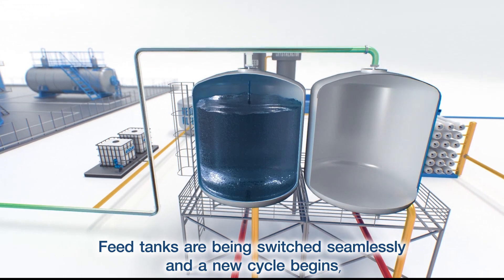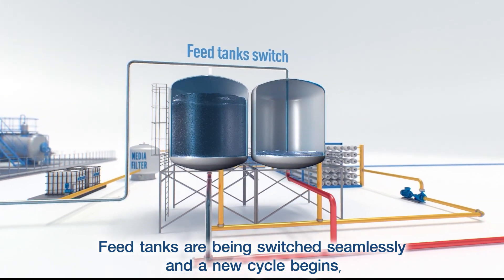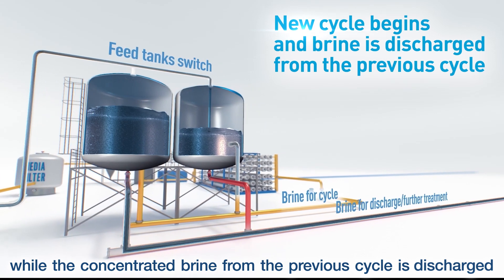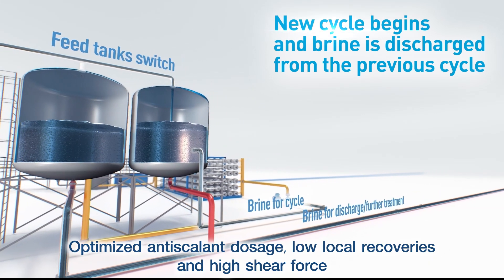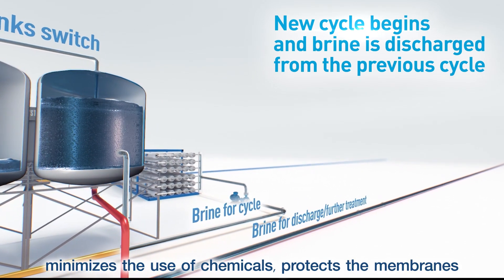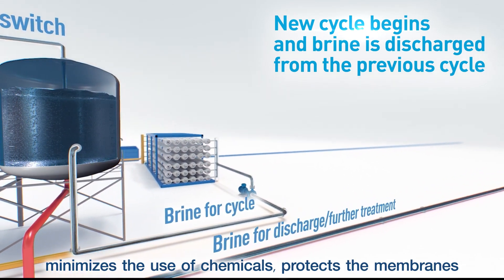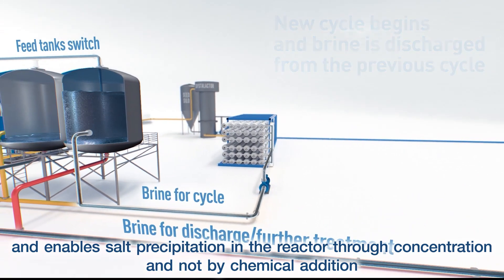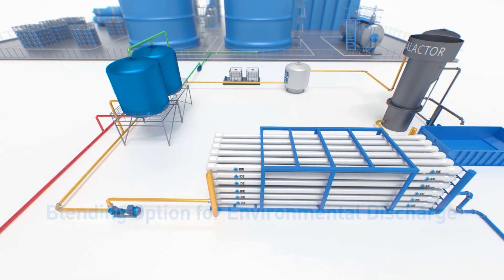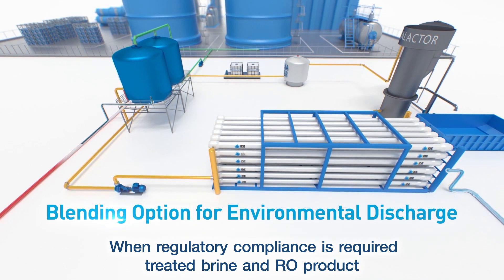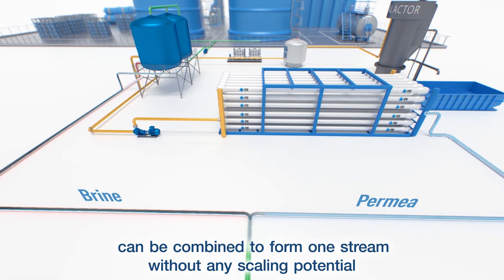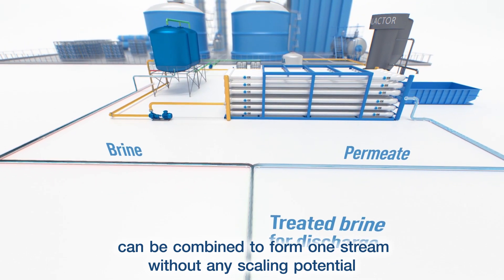Feed tanks are switched seamlessly and a new cycle begins while the concentrated brine from the previous cycle is discharged. Optimized anti-scalant dosage, low local recoveries, and high shear force minimize the use of chemicals, protect the membranes, and enable salt precipitation in the reactor through concentration and not by chemical addition. When regulatory compliance is required, treated brine and RO product can be combined to form one stream without any scaling potential.